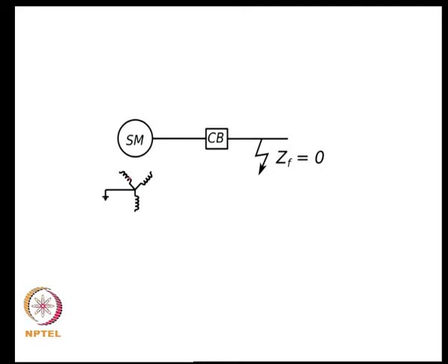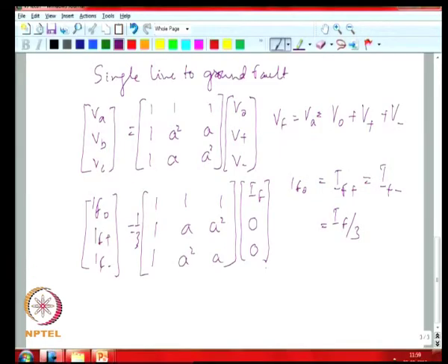So, in this model we will take say this is a synchronous machine, this might be a round rotor machine, a non-salient pole machine. So, we will take Xs to be say 110%. Your transient reactance to be 30% and your zero sequence reactance to be 10%. So, if you now look at what the model would be for a three phase fault on that particular machine.